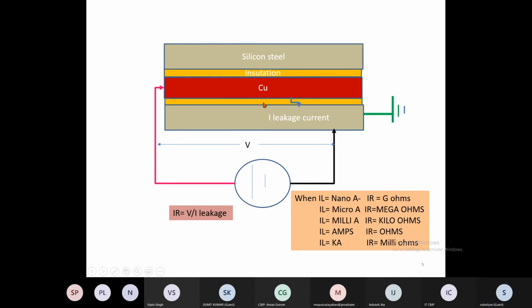Now, in order to assess the condition of the insulation, what we do is apply a DC voltage through the insulation tester or megger, and we measure the leakage current. So the voltage applied by the megger and the leakage current which flows from the current-carrying conductor, penetrating the insulation, is measured, and this is called the megger value.